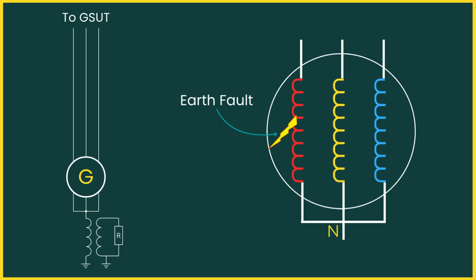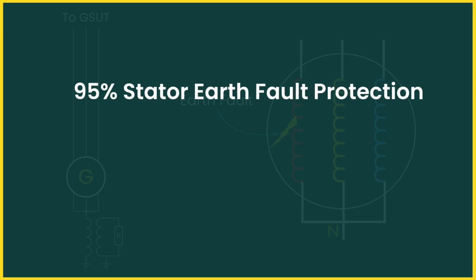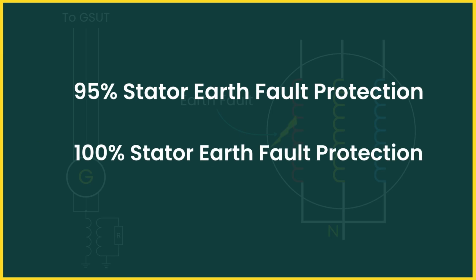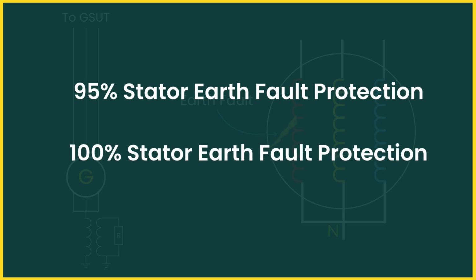That's why a reliable stator earth fault protection is essential, to detect faults early, limit damage, and prevent prolonged downtime. Now that we understand the need, let's see how modern protection schemes detect such faults. For large generators grounded through high impedance, two types of stator earth fault protection schemes are generally applied. 95% stator earth fault protection. 100% stator earth fault protection.